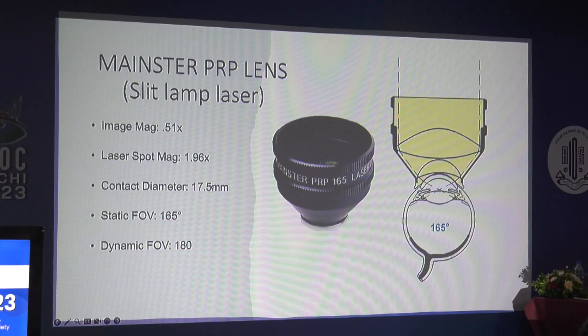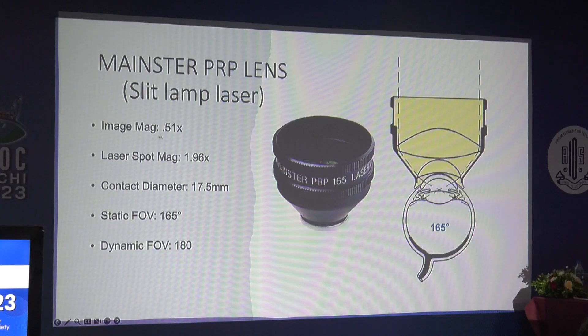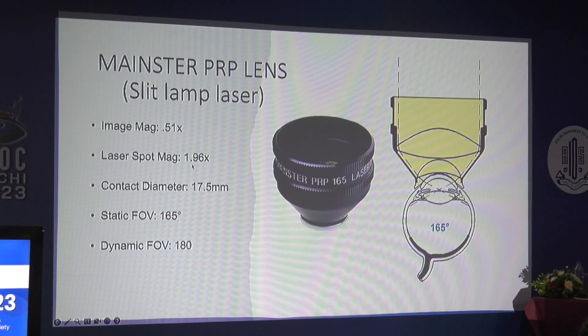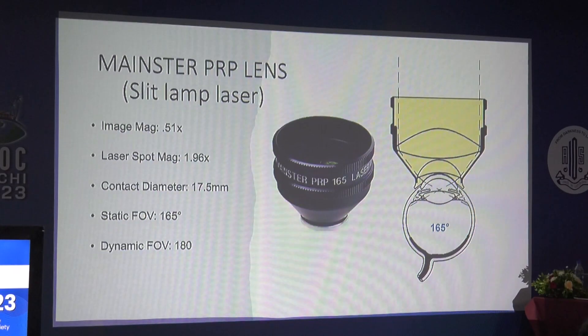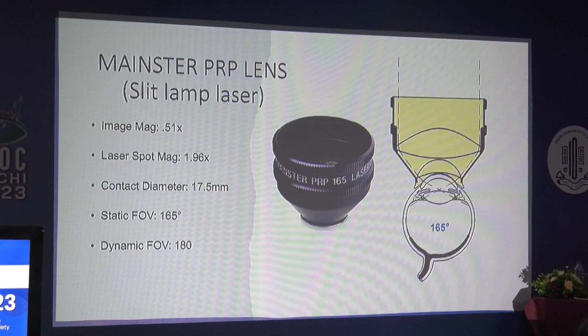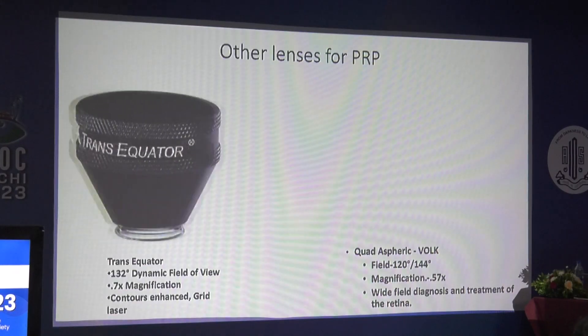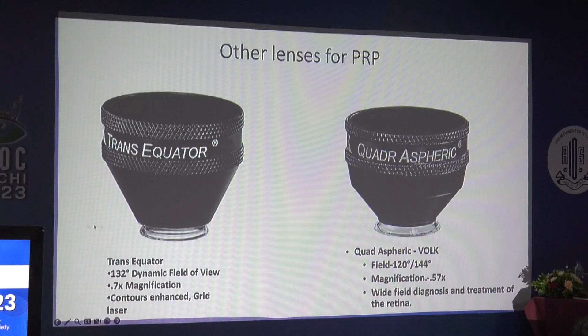This is the Mainster PRP lens by Ocular, the most common lens used for photocoagulation. The image magnification of this lens is approximately 0.5, so the laser spot magnification becomes 1.96. If you set parameters to 200 microns, your actual burn on the retina will be approximately 400 microns. It gives 165 degrees of field. There are also other lenses by Volk: the equator lens for grid laser, and the quadraspheric lens for pan-retinal laser.